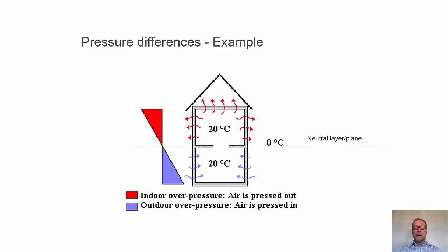And we'll have overpressure, positive pressure in the upper part of the building and in the lower part there will be under pressure. So the cold air will be pressed in by the difference in pressure inside and outside, and warm air will be pressed out in the upper side of the building.